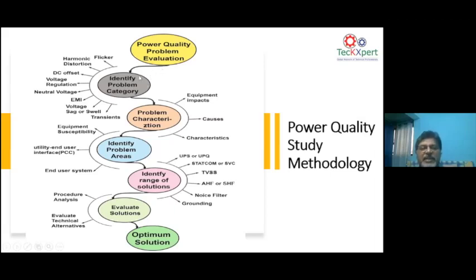When I say problem category, the problem can sometimes be due to bad earthing, which can create a neutral ground voltage. Or the problem can be due to a DC offset voltage, where some variable frequency drive or saturated transformer may be causing the DC offset. But sometimes you put the blame on harmonics. So you have to always ensure that the problem is correctly identified instead of blaming it always on harmonics.